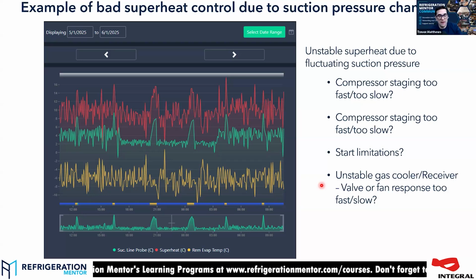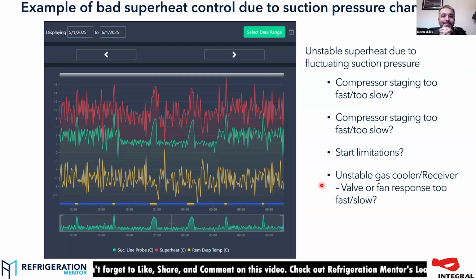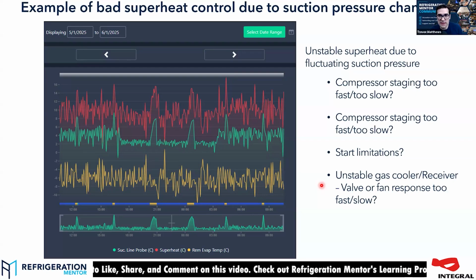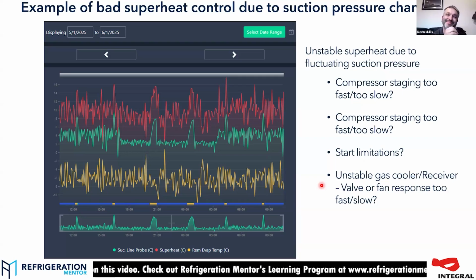I had a guy in one of my community meetups last week, I think, and he's talking about losing oil from the rack. And it's getting cold here. Like today, it's super cold, minus 20 or minus 15 Celsius. So we're real cold. And there's only some manufacturers or even some designs that are using split in CO₂. Some guys are asking me, is there split? Because this is a 16 fan gas cooler. And there is no split. There's no gas bypass on this system.